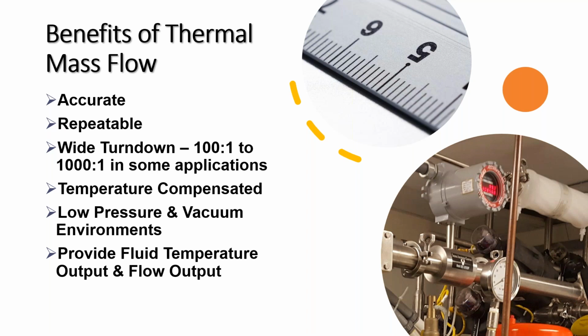And that's how we're doing that measurement. So there are a lot of other technologies out there where pressure is very key to the overall effectiveness of that instrument. Whereas in our instrument, pressure really doesn't come into play. Where we take pressure into play is more on the safety aspect. We want to make sure that we give you the right process connection. So if you're going to be running at a high pressure, we want to make sure that we give you something that will hold up and connect into your line so that you don't have anything going on there that could be a safety issue.